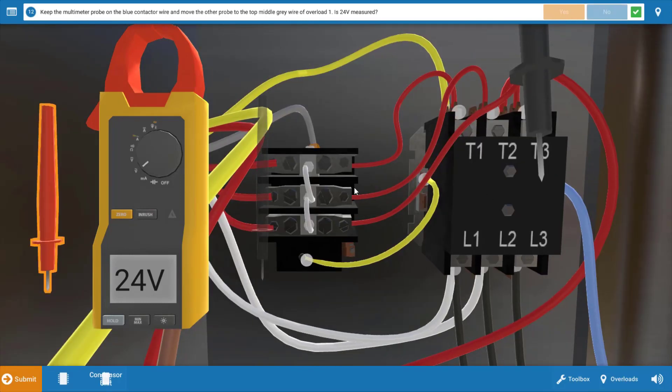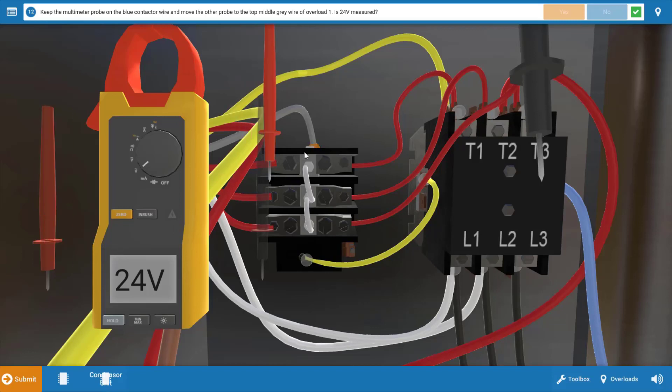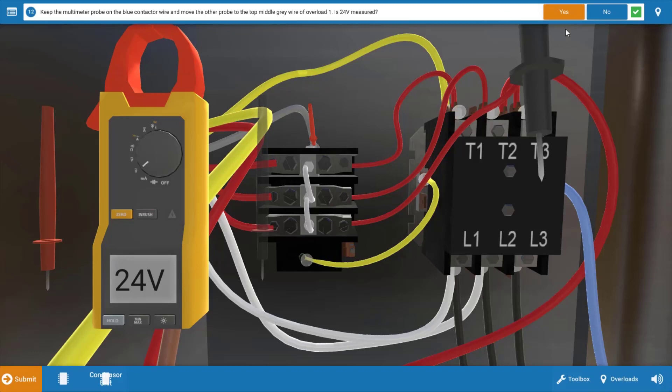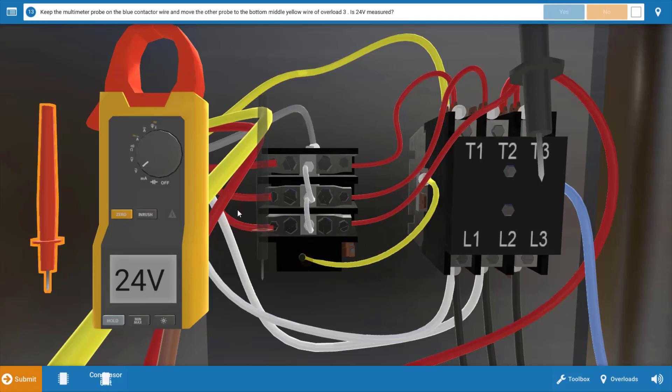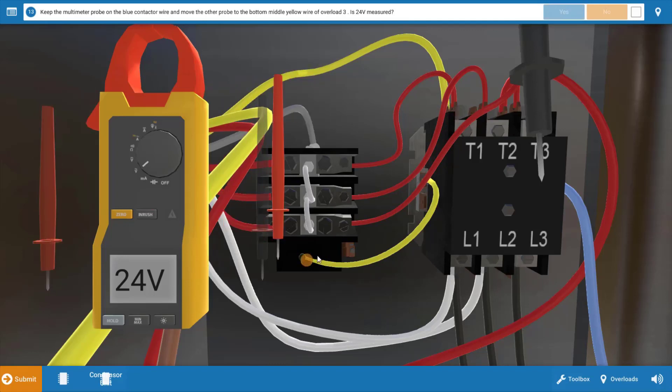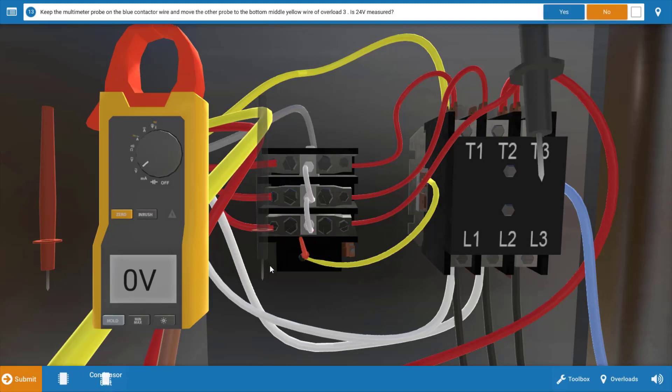Next we're going to check power going to the overload switches that are in the low voltage circuit. So we're going to place it at the top here and we have 24 volts. This is just verifying we don't have a loose connection somewhere, and we do in fact have 24, so no loose connections. Now we need to check power out of those overloads, and we can do this right at the bottom. When we do this we've got zero volts.